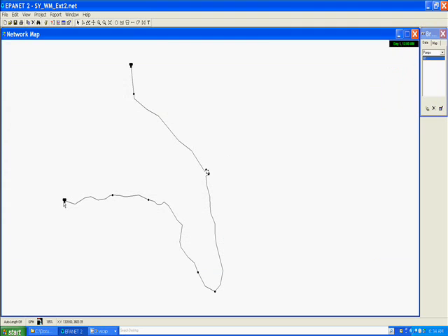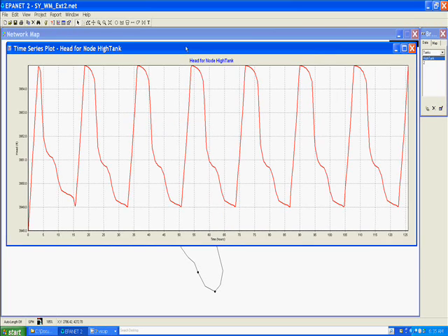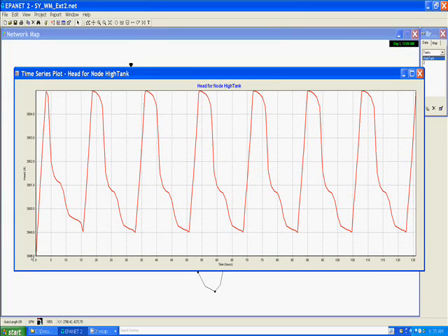We can also go ahead and look at the tank of interest over here, our proposed tank, and see what's happening with that. See if we get a similar kind of symmetry. I'm doing a time series again. This time I'm going to choose the parameter of head, and that's the liquid level elevation inside of the tank. And we can see here again over the 7 days we've got a fairly good symmetry with the tank starting off with a liquid level of about 5 feet in the tank.